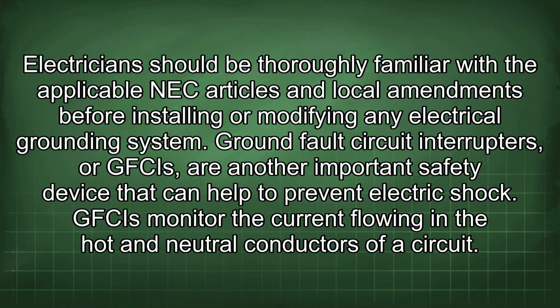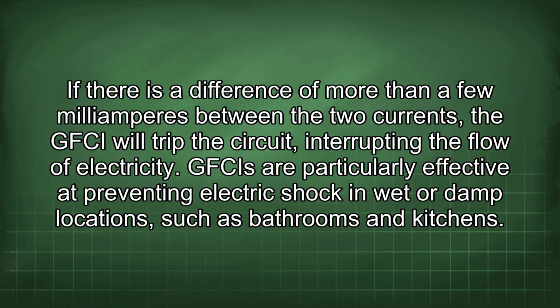GFCIs monitor the current flowing in the hot and neutral conductors of a circuit. If there is a difference of more than a few milliamperes between the two currents, the GFCI will trip the circuit, interrupting the flow of electricity. GFCIs are particularly effective at preventing electric shock in wet or damp locations, such as bathrooms and kitchens.